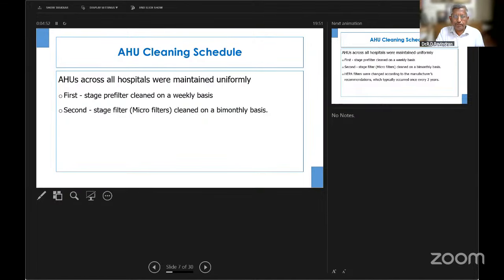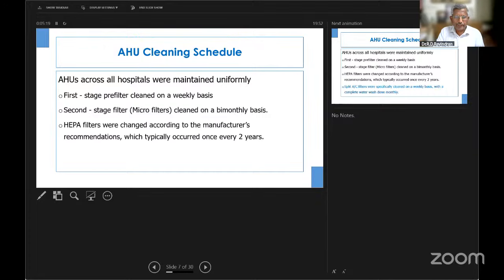We have a standard cleaning protocol for all our operating rooms, especially the air conditioning systems, because maintenance is important to get the best out of them. The first stage pre-filter is cleaned weekly, and the second stage or micro filters are cleaned once every 2 months. Wherever we have HEPA filters, we typically change them once in 2 years, usually within that period.